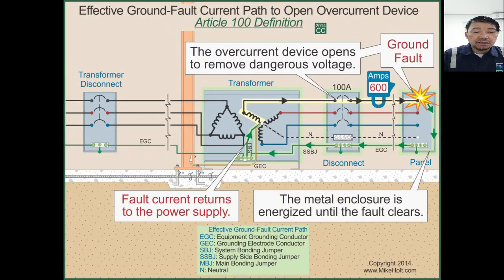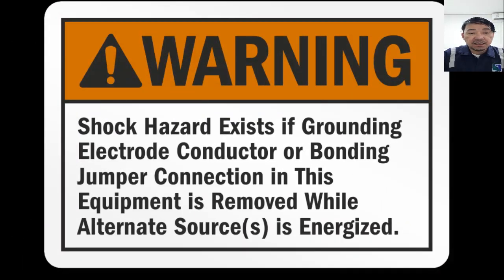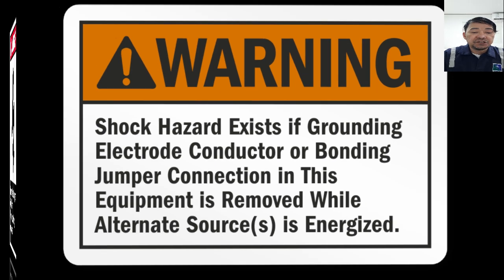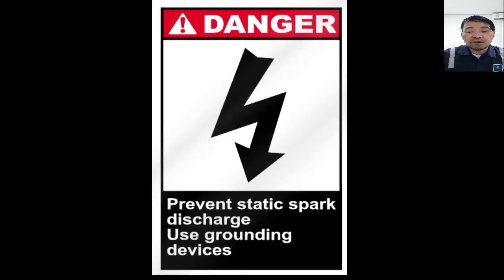Facilitate. The purpose of the equipment grounding and bonding conductor is to provide the low impedance path to the electrical supply source to facilitate the operation of circuit protection in order to remove dangerous ground fault voltage on conductive parts. And the last is safety. In general, grounding and bonding promote safety of the personnel and electrical installation.